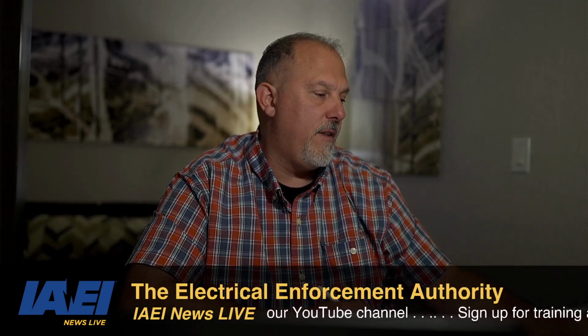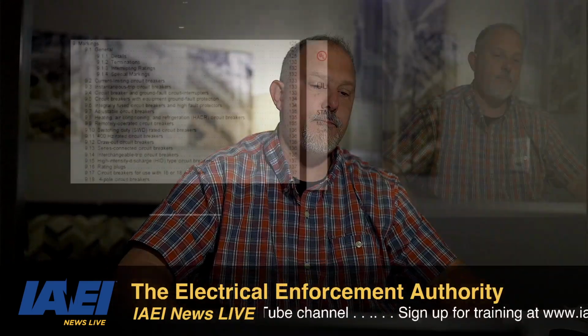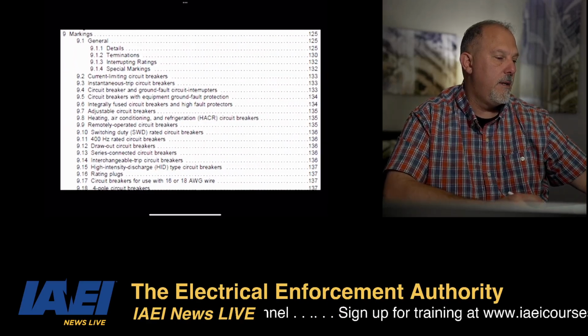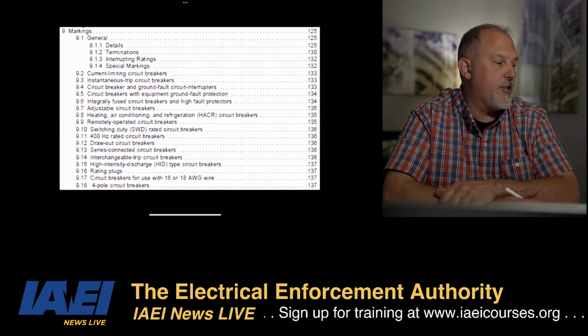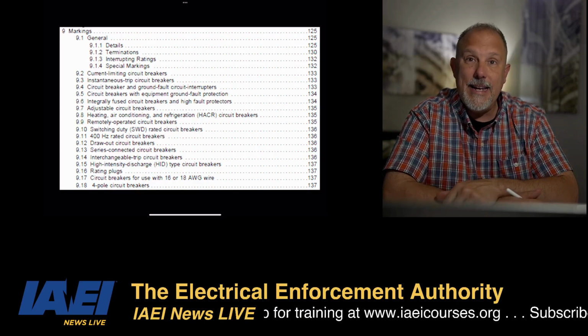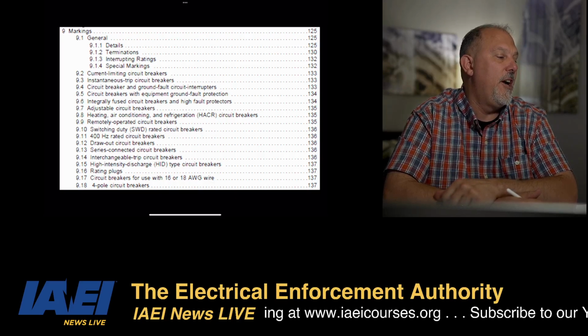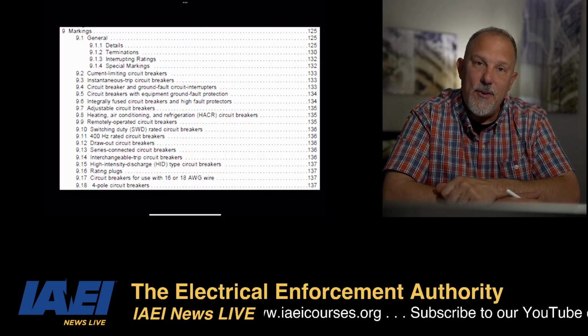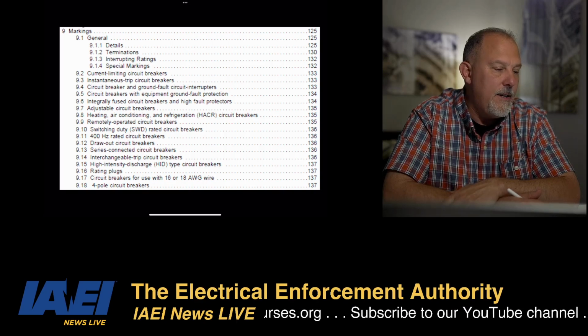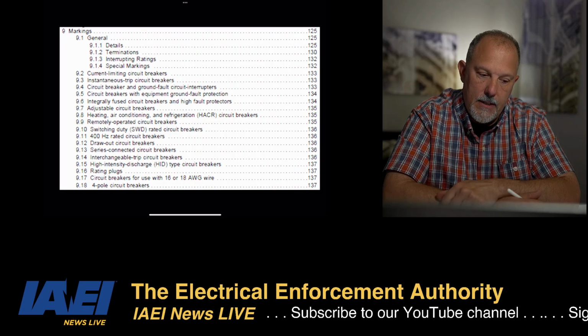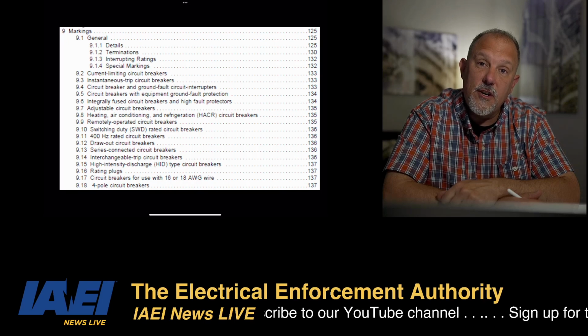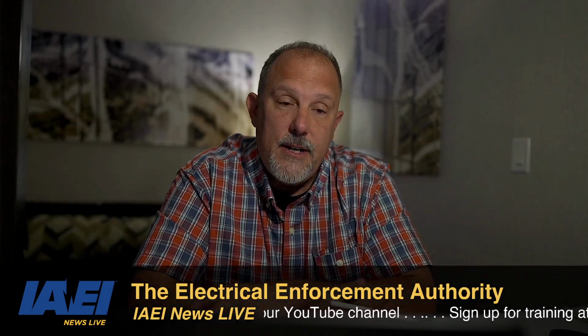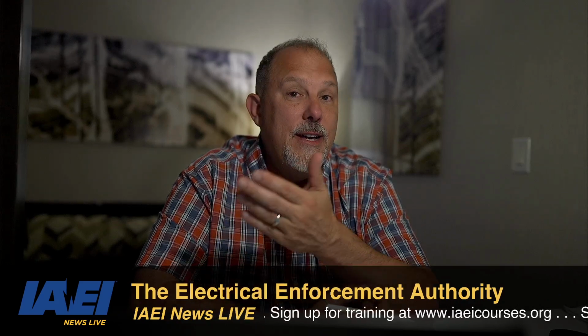Yeah, so there's a whole section in UL 489. Here's the section in UL 489. So section 9 is titled Markings. General. You have your general information. You got your interrupting ratings, any special markings. You got current limiting circuit breaker, instantaneous trip circuit breakers, circuit breakers and ground fault circuit interrupters, circuit breakers with equipment ground fault protection. So these are all the different types of circuit breakers that you may have that you have to provide special marking requirements. So if a circuit breaker has some functionality that is a little different than just a standard thermomagnetic circuit breaker or even electronic trip circuit breaker, if there are special features that that breaker brings to the table, then the standard is going to tell you any special marking requirements.